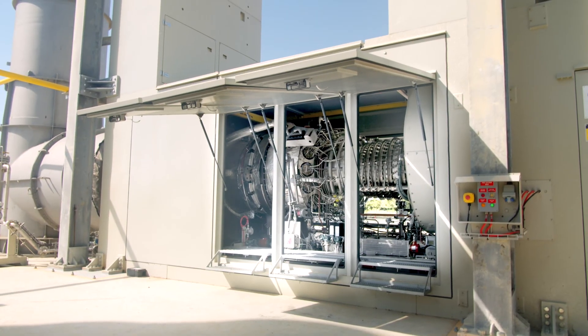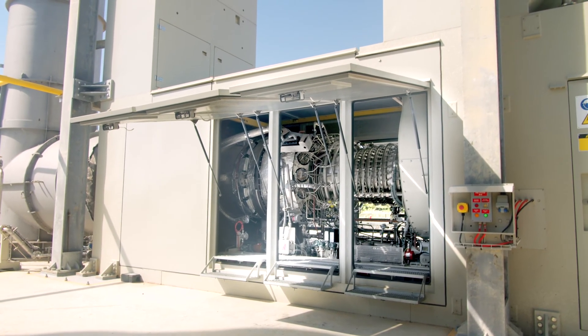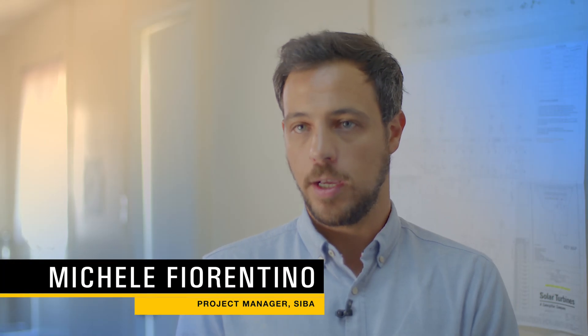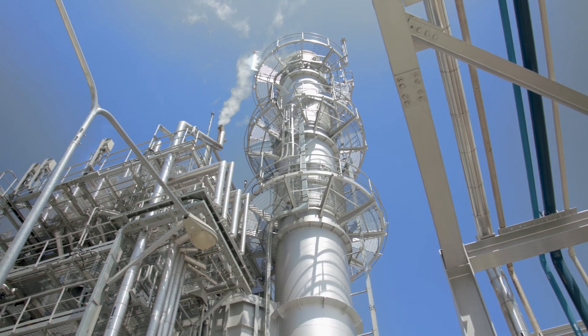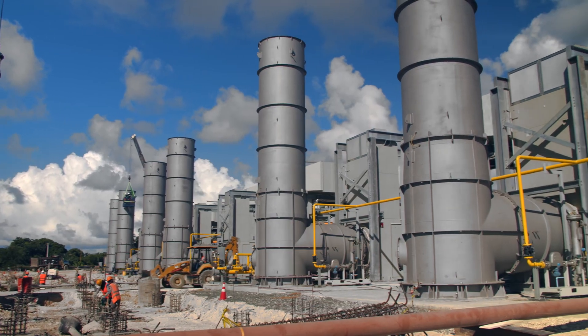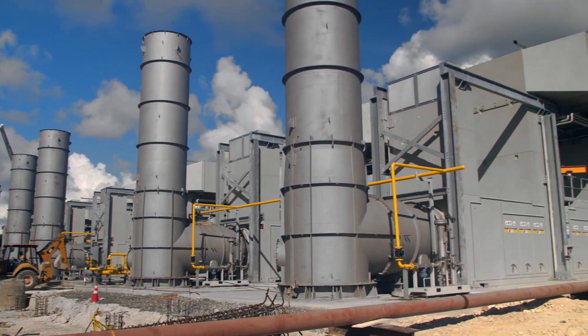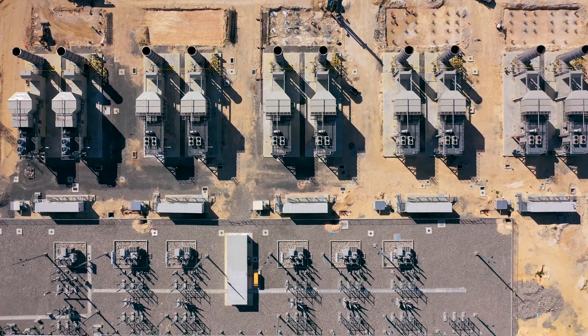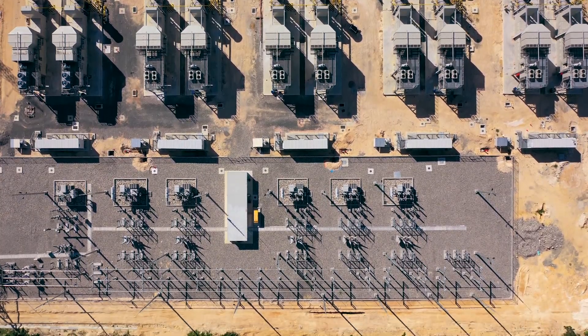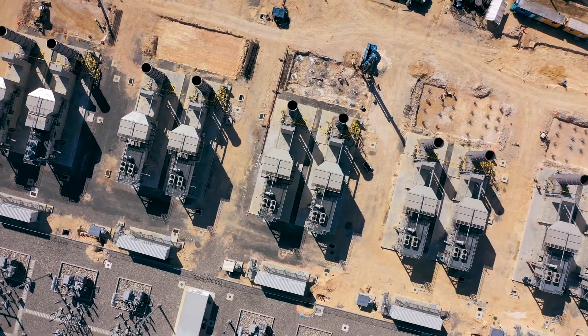Solar Solutions allows for efficient co-generation applications. We're using the heat produced by the gas combustion, and with the HRSG we are making steam which goes to two steam turbines — adding another 80 megawatts to the 190 which are produced now. So we are making the process more efficient: with the same input, we're producing more megawatts.